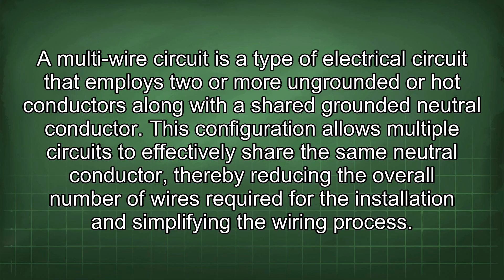A multi-wire circuit is a type of electrical circuit that employs two or more ungrounded or hot conductors along with a shared grounded neutral conductor. This configuration allows multiple circuits to effectively share the same neutral conductor, thereby reducing the overall number of wires required for the installation and simplifying the wiring process.